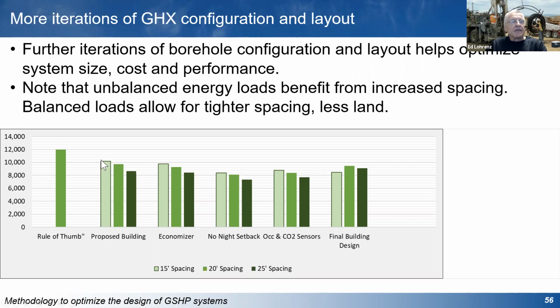In this case, the building that was originally proposed required just over 10,000 feet of drilling. This one is about 8,500. That's a fairly significant difference simply by increasing the spacing between the boreholes. If the loads are fairly balanced, there's less of a difference. You don't see that.